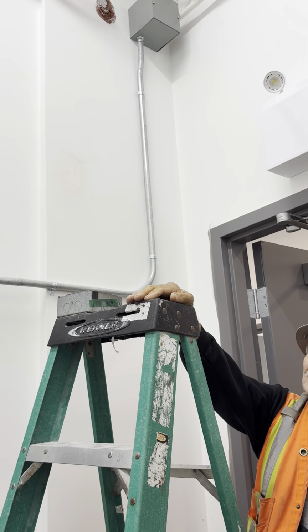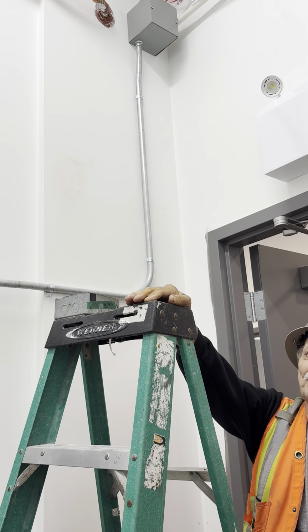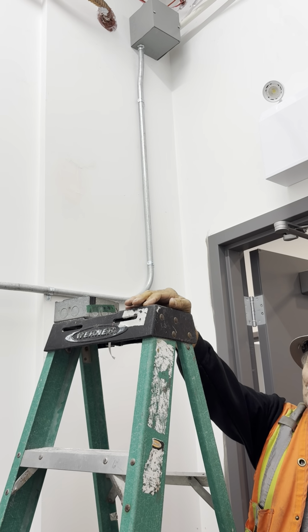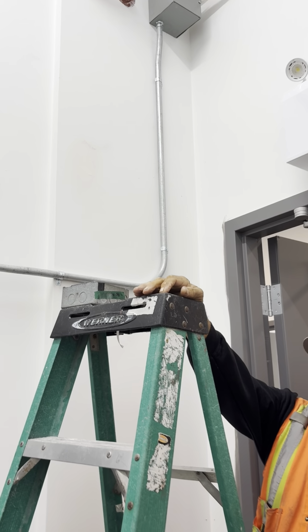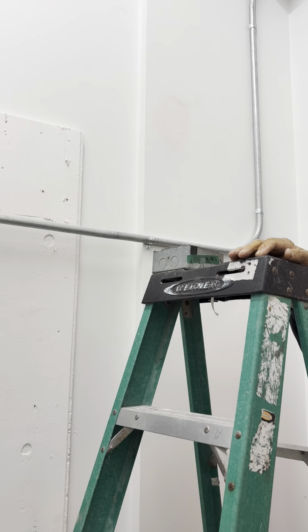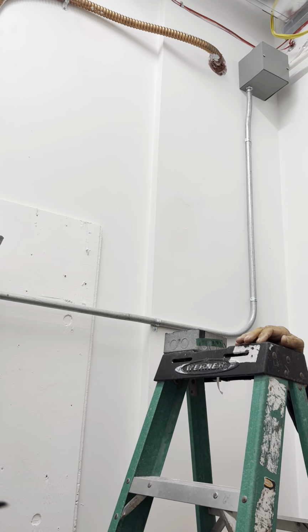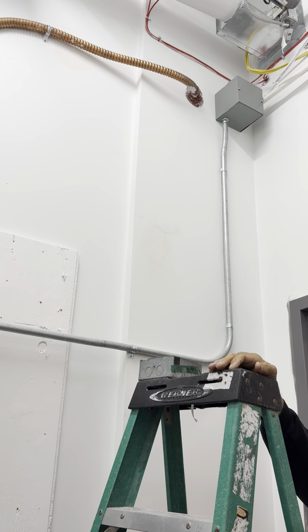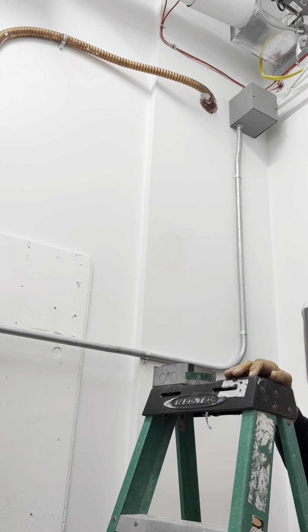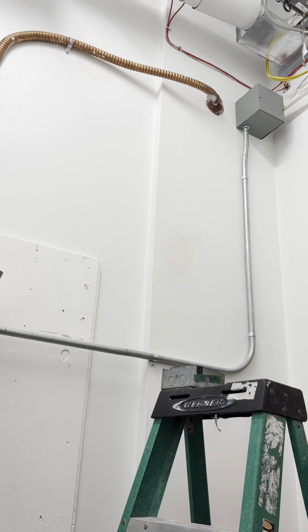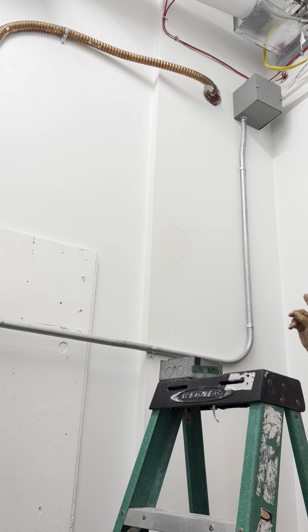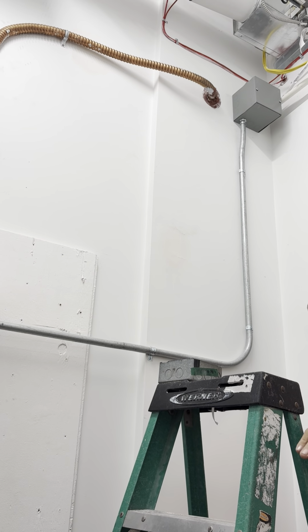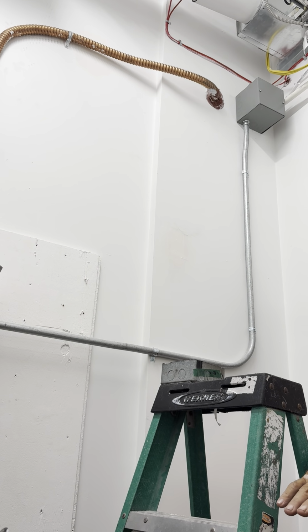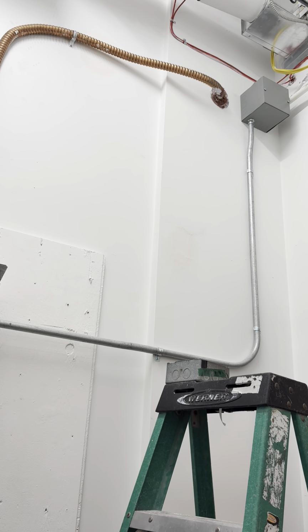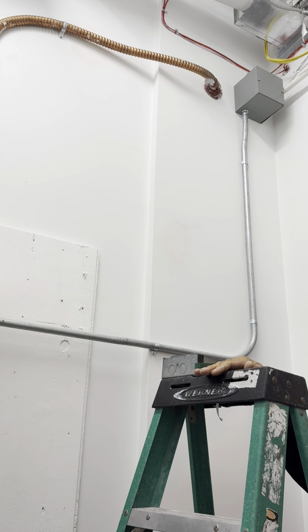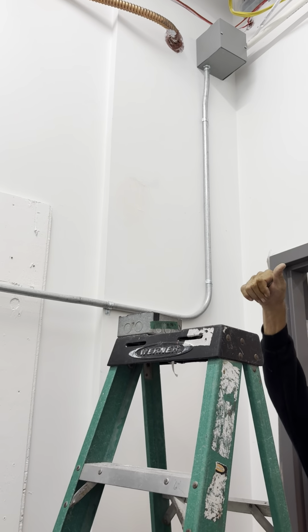Every space that has a fire damper, with air going from the corridor into the room, has a smoke fire damper. So if the whole building has a fire alarm, does it trigger all of them? It won't trigger those. Only if this room here gets smoke in it will it trigger. If this room had a heat buildup of 165 degrees that hits the exhaust, it would shut it down. So at any time you lose your exhaust in here, check it independently.